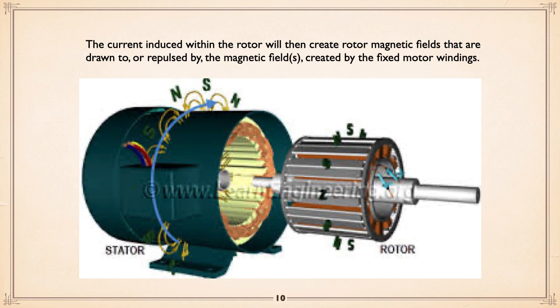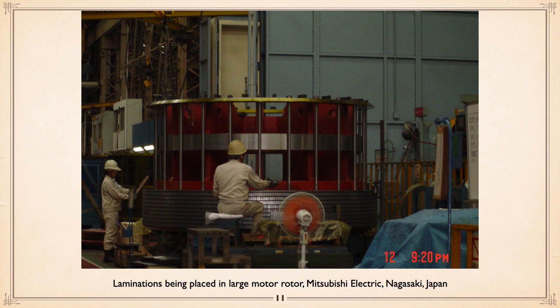Magic. In fact, a lot of people, when they first go to start a motor, don't worry about rotation, just see which way it's going, and then just cross two leads if they don't like the direction it's going. And motors get bigger. This is a motor that actually is being put together vertically, and you can see, pardon me, rotor. This is the rotor, not the stator. I apologize. Imagine how big the stator is for this thing. But there's the rotor, and they're putting on the laminations. There's the bars that go up and down, and it's a pretty big motor.